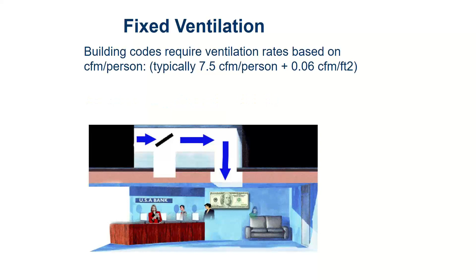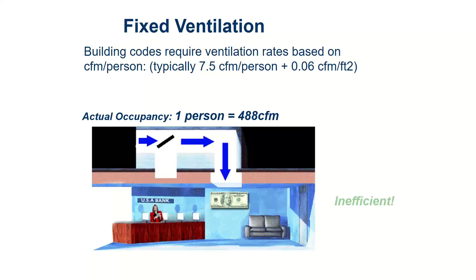And later on, when this lady's by herself counting up all the cash, it's still 488 because the system doesn't know there's nobody there. It just doesn't know. So what I want to do is give it a way to know. I want to have it count the people and then change the ventilation for the amount of people. Let's get the right amount of air to the right place at the right time. And how are we going to do that? So the way we're going to do that is by measuring CO2 in the space, carbon dioxide.